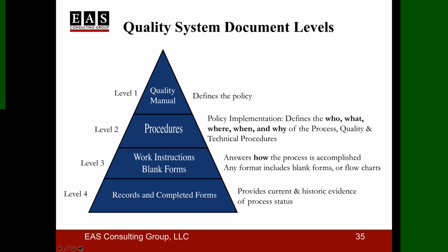So, for example, the quality policy may state, we're going to have a quality system in place, in which we're going to design product, we're going to manufacture the product, we're going to service and install the product. Very generically, it may even quote the different regulations, such as 820.30 for design controls and others. The SOPs go into that, so you can have a procedure about design controls, about quality auditing, about purchasing controls, complaints, etc. Then the work instructions are how you're going to do that.